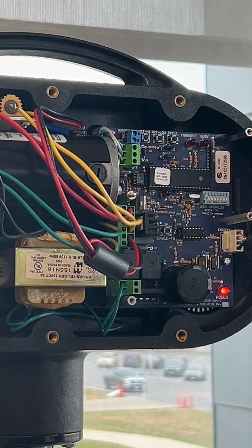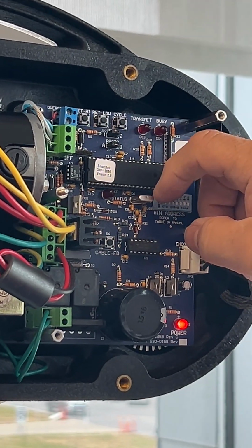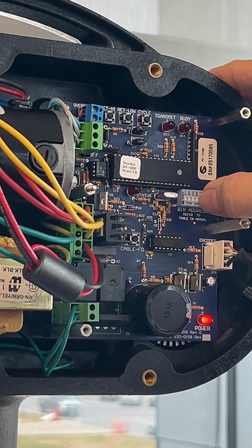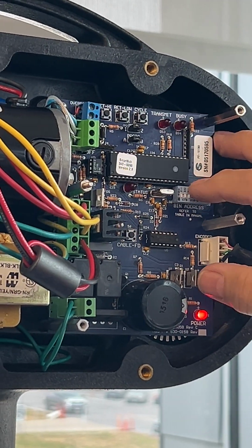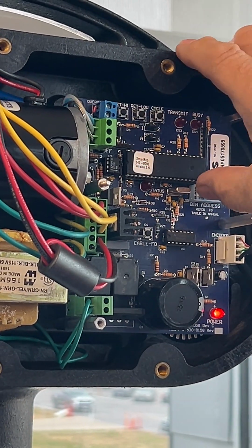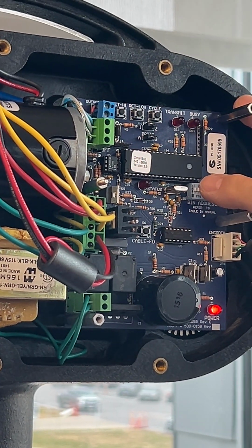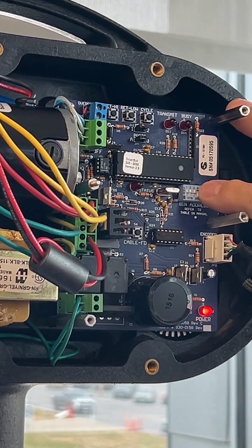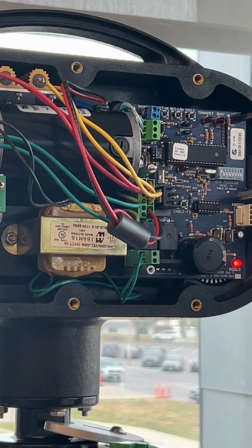Okay. What would it look like for switch number 8? Switch, you mean for address 8? Address 8, yeah. Address 8, then number 1 would be down and number 4 would be on, because number 4 has a value of 8. Now, for address 7, the first 3 switches would be up, because it's a value of 1 plus a value of 2 plus a value of 4, so that's 7. See. Okay. Okay, so I'll leave just switch 1 up.